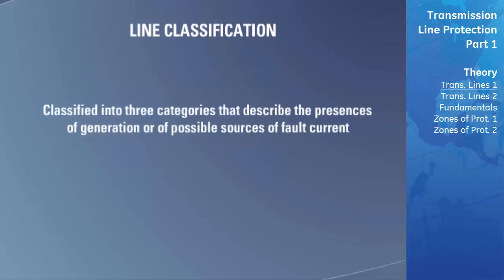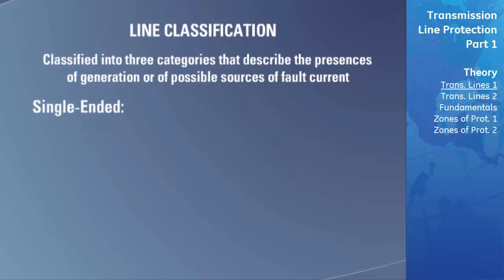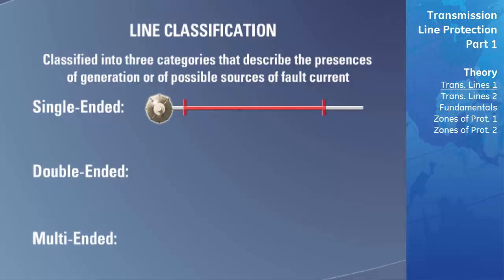Transmission lines are classified into three categories describing the presence of generation or possible sources of fault current at the line's boundaries. These are single-ended, double-ended, and multi-ended. A single-ended line, also called a radial line, has a source at only one end and is used to deliver power from the source to a load at the other end. Whenever a fault occurs, there is only one source of current to feed the fault.